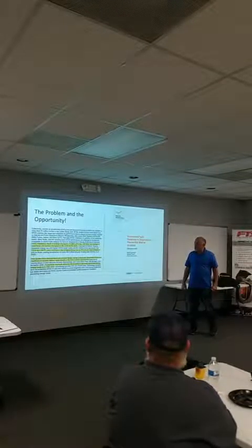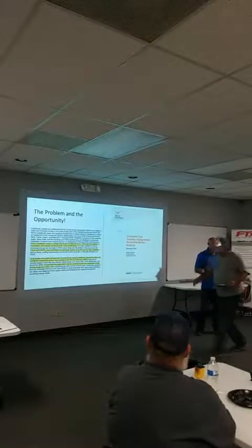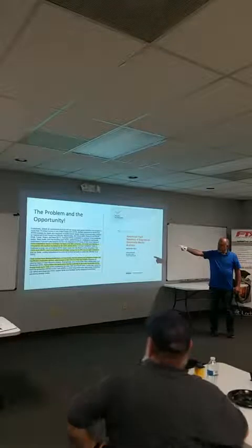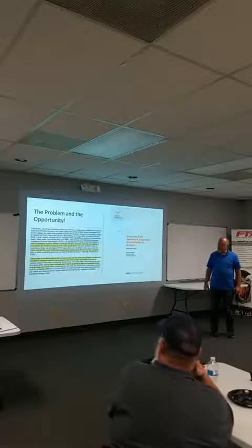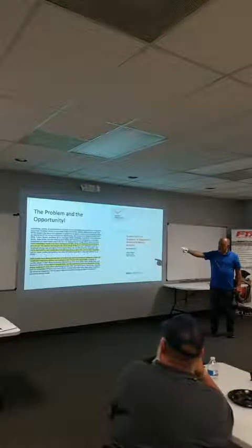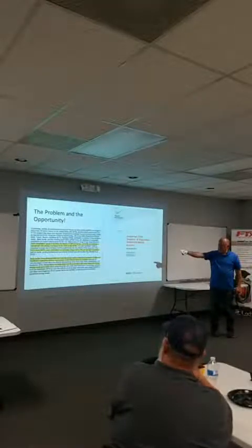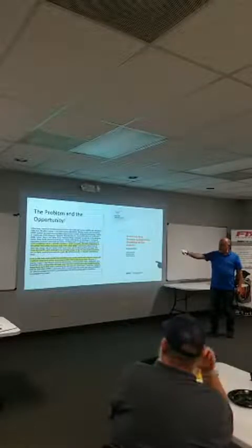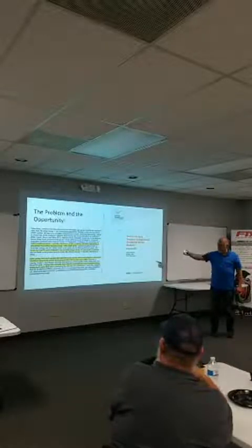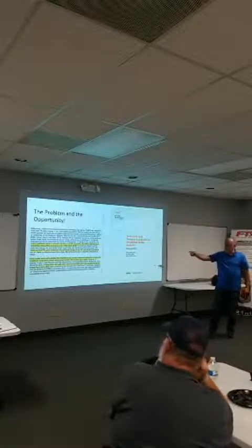Central air conditioning and air source heat pumps, DOE did a study. 70 to 90% of homes have at least one fault. You can apply this right across to commercial, it's the same thing. Commercial guys are pretty much in the same boat as residential guys. That number increased to 90 to 100% when duct leakage is included. Poor installation may use 9% more energy than ideal. The most common faults were inadequate refrigerant charge and insufficient evaporator airflow, in 50 to 72% of central air conditioners and air source heat pumps. Fixing those two problems alone could reduce energy loads by 5 to 10%, right?